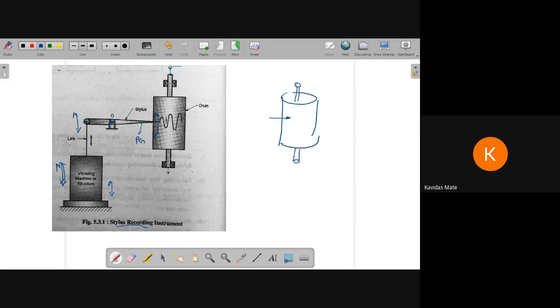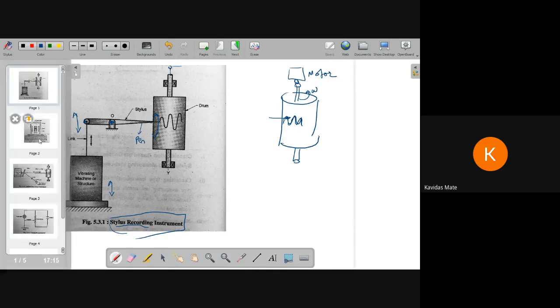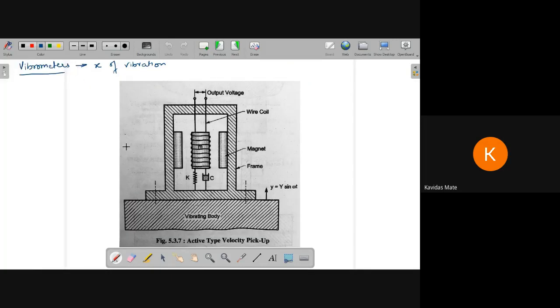The pen is attached on this paper drum, which rotates at a constant omega driven by a slow speed motor. Whatever vibrations occur are recorded on this particular paper. So this type of instrument is called a stylus recording instrument — we have a stylus, and it is recorded on this paper. This is one type of vibrometer where we measure the amplitude of vibration.